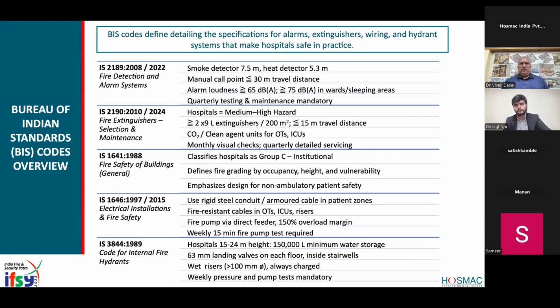Got that. Just one thing I wanted to add in the first column, fire detection and alarm system, where there is a noisy area in the hospital, sir. If the alarms will not be possible to hear, strobe lights are used. So strobe lights are nothing but flashes. Whenever the fire is caught, it flashes light, so that it can be very easily seen visually.